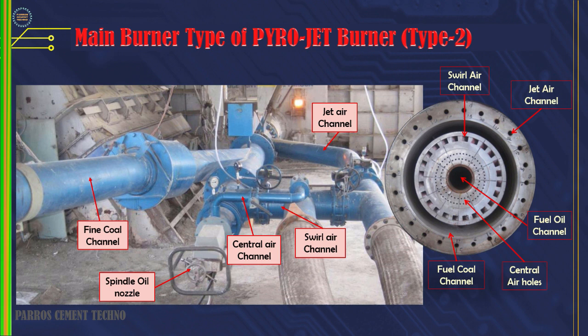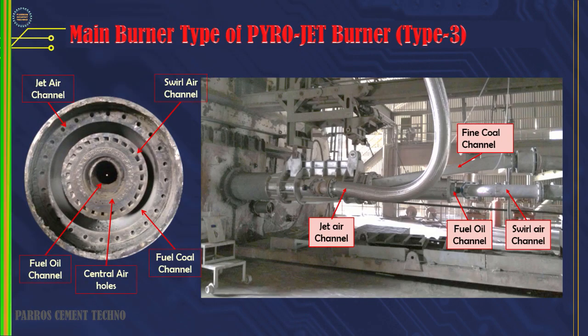This type of PyroJet burner is slightly different from the previous PyroJet, because it does not use cooling air between the burner casing and the castable burner. Primary air pressure using a roots blower is between 300 to 800 mbar for axial, and the radial blower is 150 to 200 mbar. The next type of PyroJet burner has a simpler air duct from the blower. The axial air pressure ranges from 300 to 600 mbar and the radial or swirl air pressure is 150 to 200 mbar. Primary air setting uses a speed roots blower setting.